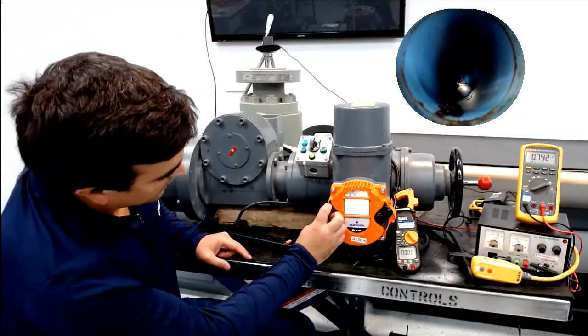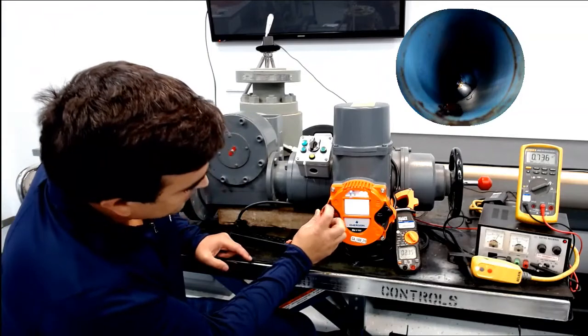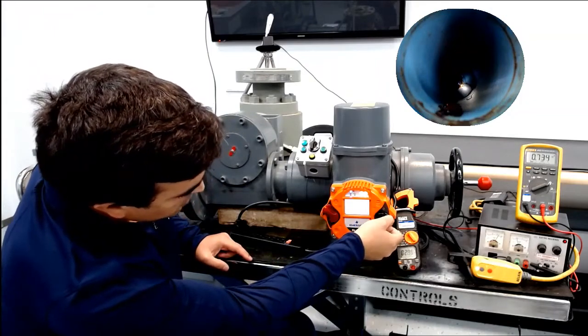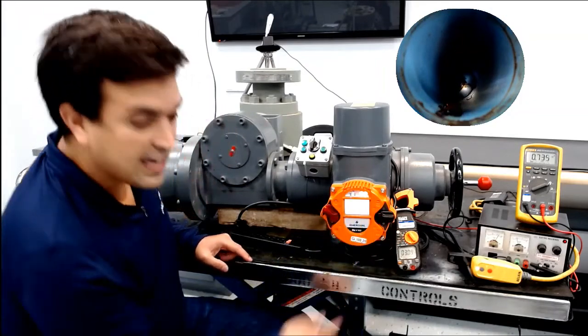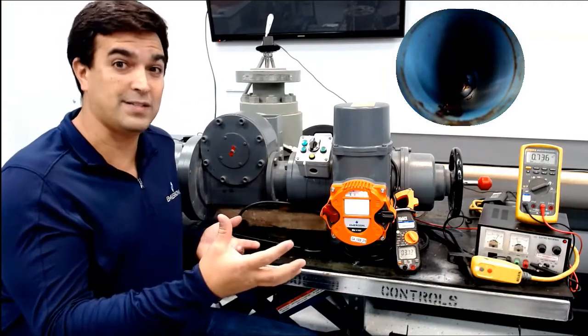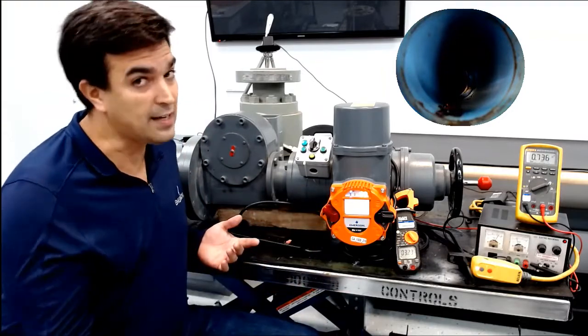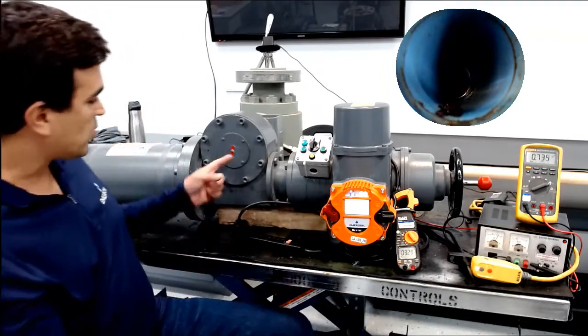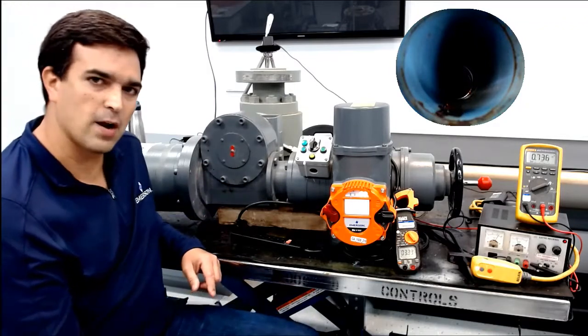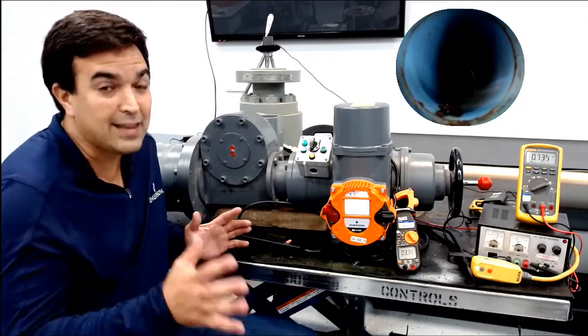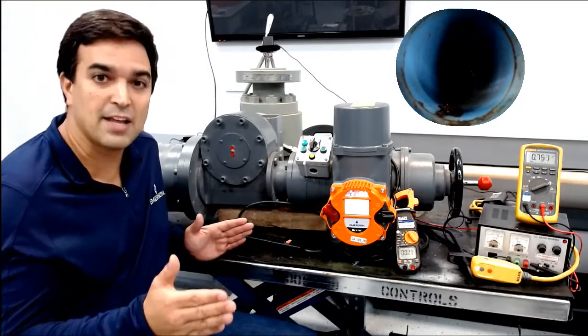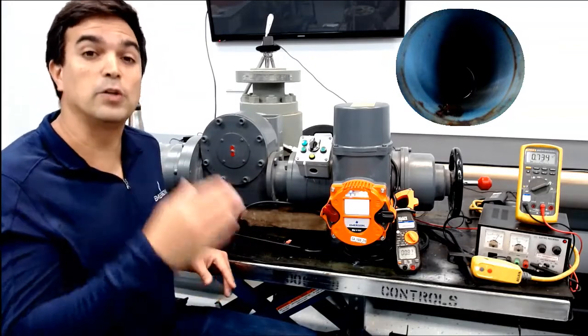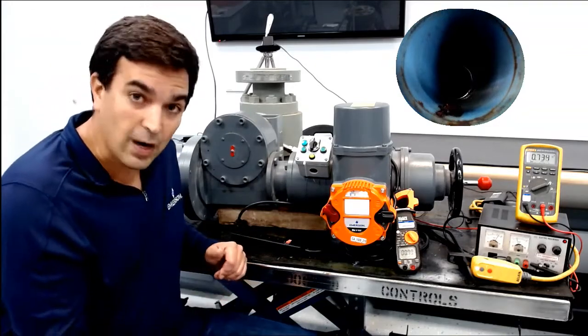You will see here that you can have the signal, and you will see PVST, which means that the partial stroke was activated. It's going to return the valve to 100% open as soon as it meets the timeline of less than 30 seconds, which it met, and it's going to tell you okay, so let me do the second one.